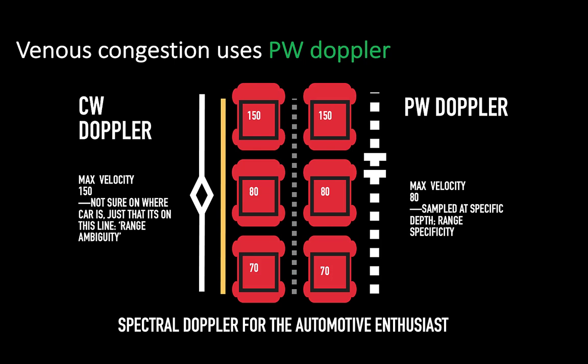The difference between continuous wave Doppler, or CW Doppler, and pulse wave Doppler, or PW Doppler, is timing of pulses and listening pattern. Pulse wave Doppler sends a pack of signals and then stops sending signal to listen for the returning signal. As every emitted pulse is paired with a corresponding return signal, it is possible to determine where the reflection has occurred and calculate the distance of the reflector.